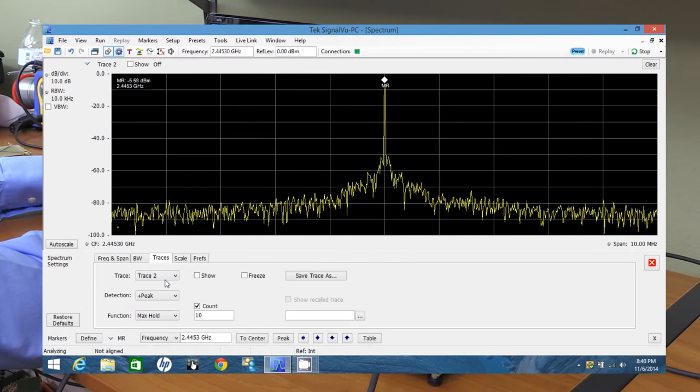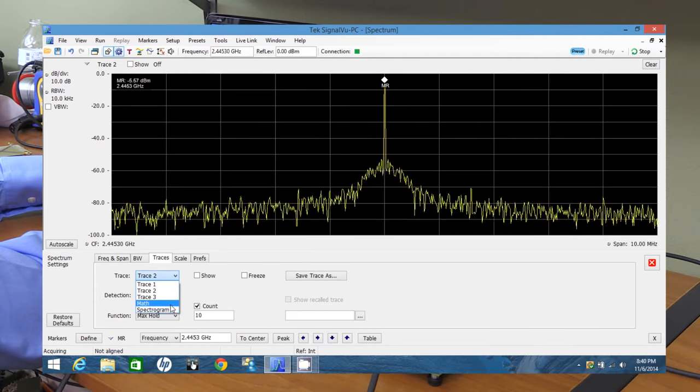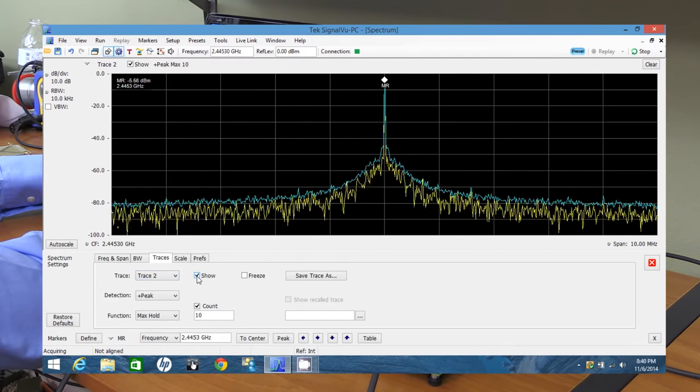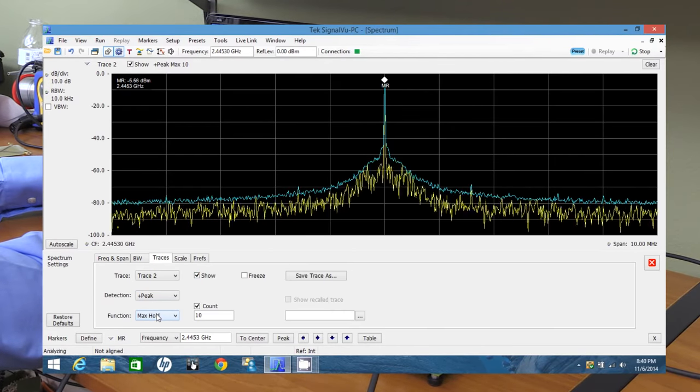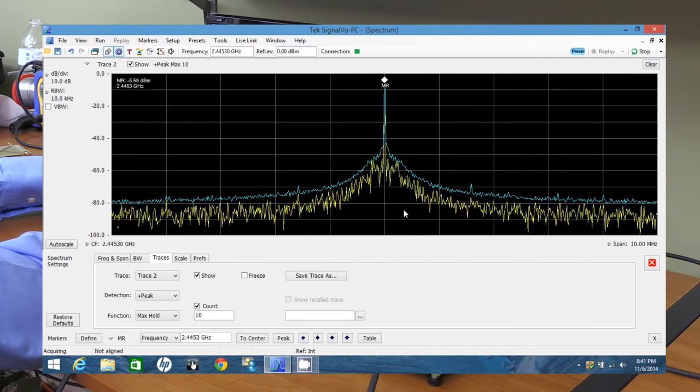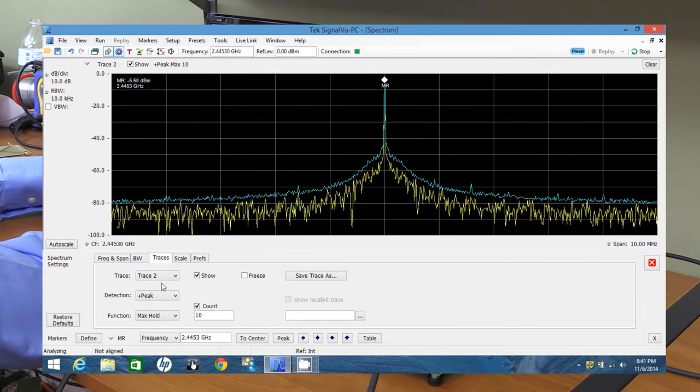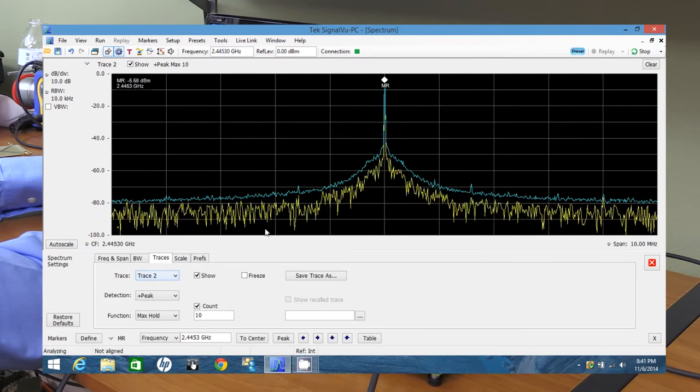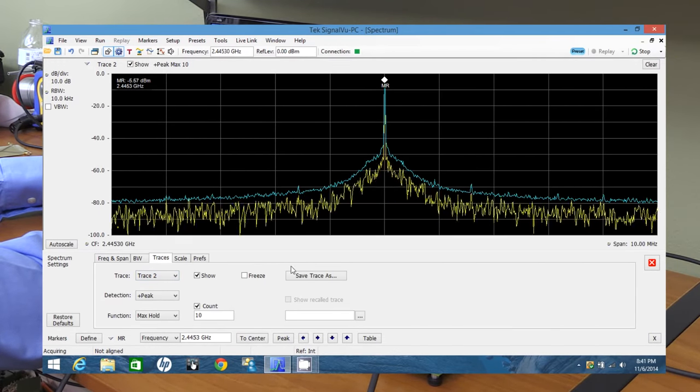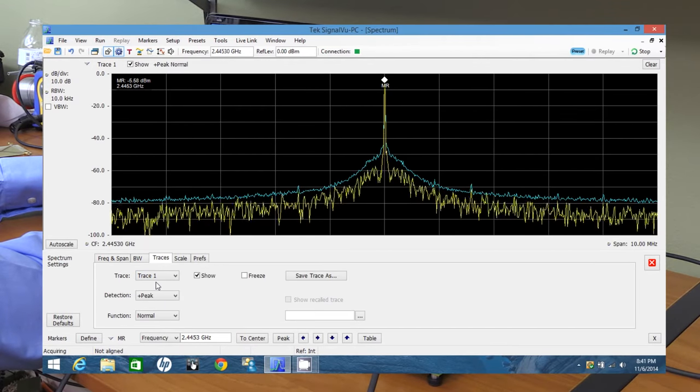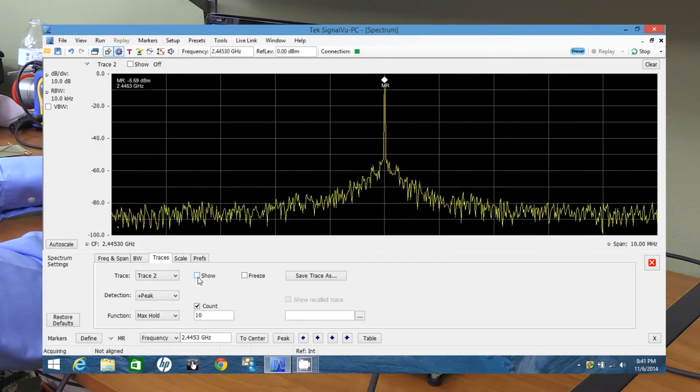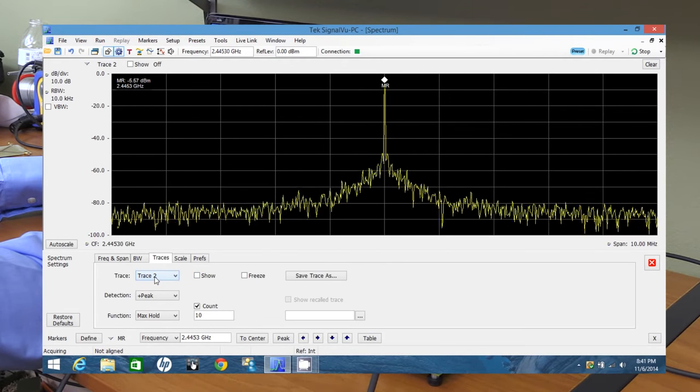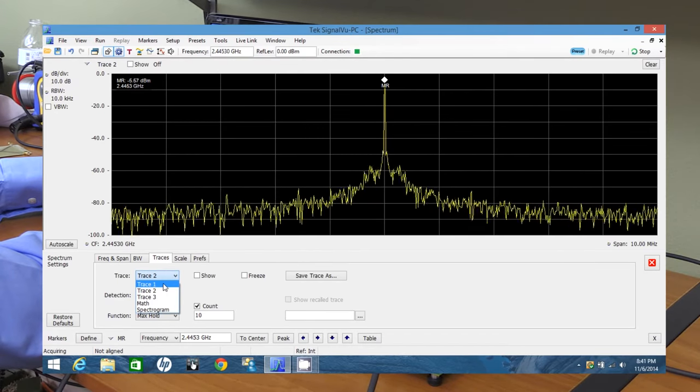And we can add a function like average. Or we can do a max hold. Default is normal. That's what you just saw. And we can add another trace. So actually, we can add multiple traces. We can even do math here. And let's take the second trace, click show. And let's make that a max hold. Seems like that was the default. And you see we got two nice traces here. And one thing you need to be certain is if you have trace two selected now and you go back to your markers, the marker will be on trace two. And sometimes that'll mess you up.